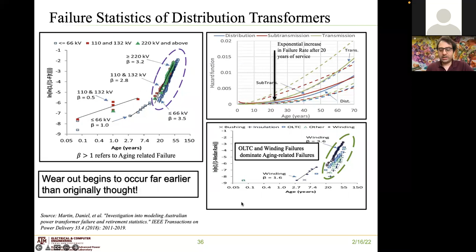The picture on the bottom is for distribution transformers, and after about 20 years of age, failures in the OLTC dominate the failures happening in distribution transformers. So we conclude that for distribution transformers, aging failures dominate, and among aging failures, it's the OLTC and winding failures that dominate.